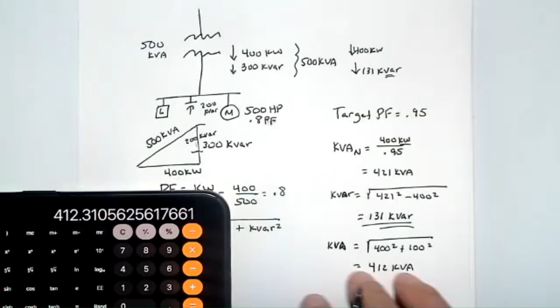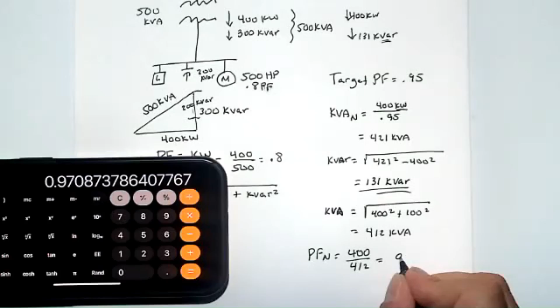And so now my new power factor is not 0.95, it's actually better than that. It's 400 divided by 412, and my new power factor is 0.97. So what that means is I now have on my transformer up here 400 kilowatts still flowing, 100 kVAR flowing, and my new power factor is 0.97. And that's how I do my power factor correction, by adding a 200 kVAR capacitor to an existing load.